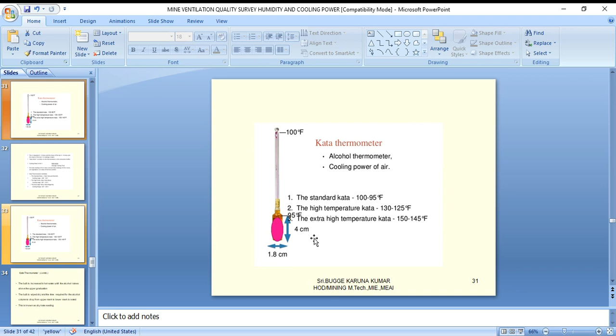This is repeated 4 or 5 times, and the mean of the last 3 or 4 readings is taken. The Kata factor is written on the thermometer or on the instruction leaflet. Cooling power of air is equal to the Kata factor divided by the average cooling time. That is the standardized formula for whatever model we have. This is the standard formula: Kata factor divided by average cooling time from 38 degrees to 35 degrees.